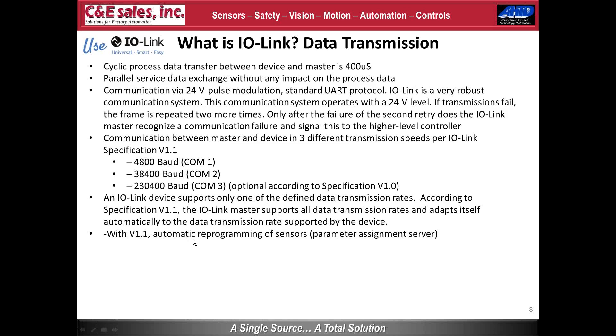A version 1.1 master can automatically detect the device's baud rate and set its own transmission rate accordingly. Version 1.1 also enables automatic reprogramming of sensors. If you replace a sensor and don't want to reprogram it, the master can pull all parameters from the existing device and then transmit that parameter list down to a new device. Both the master and device must be IO-Link version 1.1 for this feature.